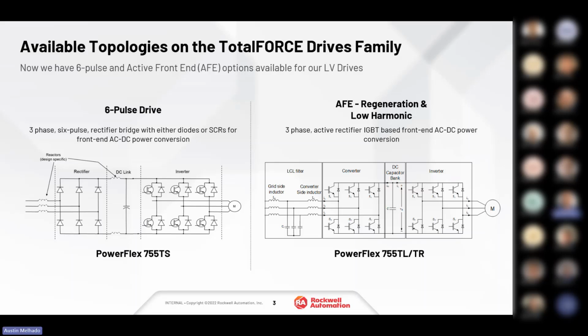We're going to be focusing on the 6-pulse VFD, which is the TS, similar to the 753, 755, and any standard VFD. Six SCRs in the front rectify our AC voltage to DC, then out to the DC bus to the 6 IGBTs in the back end, and that's where we get our pulse width modulation. Just a little power topology review there.